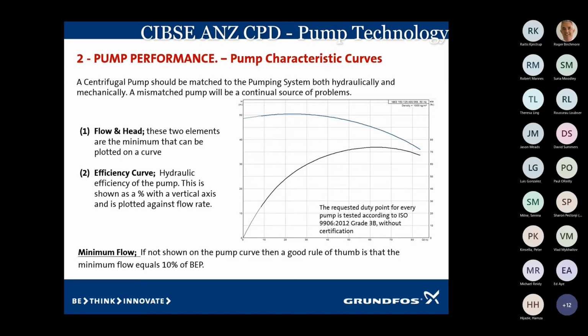And it's relative. I guess the best way of looking at it is, if you imagine you've got a hose without a nozzle on the end of it, and you're trying to get water to one end of the garden, and you can't get it down there. What do you do? You put your thumb over the end of the hose, and all of a sudden you get the water to the other end of the garden. What you're doing is reducing the flow, but increasing the head. So at 70 litres a second, you take your thumb off. If you put your thumb on the end of the hose, then you'll increase the pressure, but you'll reduce the flow rate.